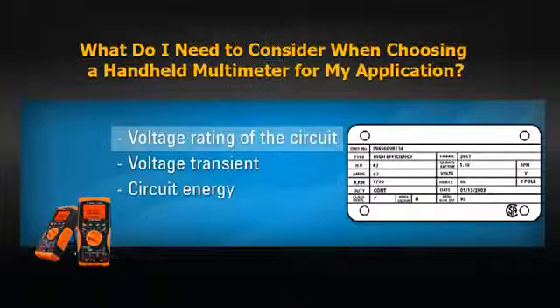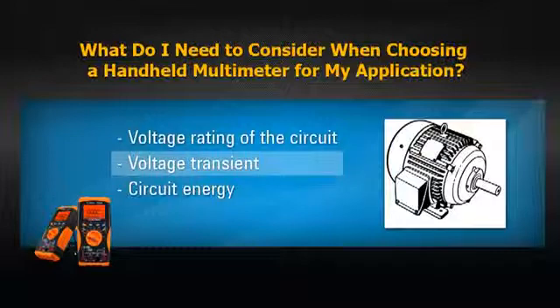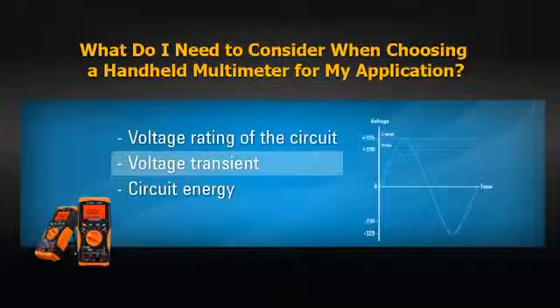The first consideration is the rated voltage of the circuit you are measuring. The multimeter you select should have sufficient voltage rating for the circuit under test. Secondly is protection against high voltage transients caused by load switching or lightning storms. These transients can vary from a few hundred volts to 8,000 volts, lasting up to a few hundred microseconds.